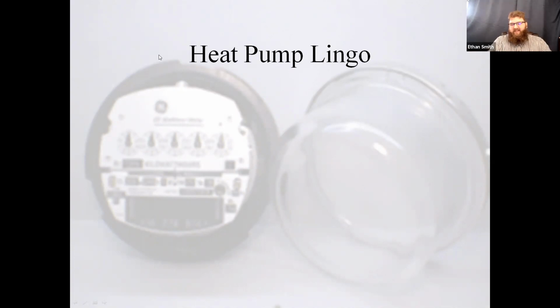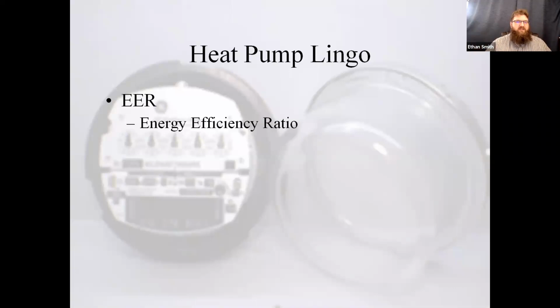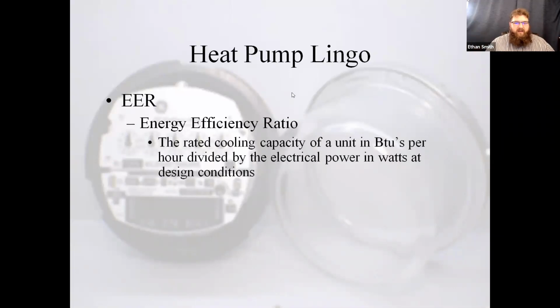Okay, so heat pump lingo, guys. There's a few terms that we need to be familiar with if we're gonna talk about heat pumps in an intelligent fashion. So let's get some of the vocabulary out of the way here. EER is a term we use more commonly in heat pump specific, and that's just the energy efficiency ratio. So this is a momentary glimpse of how efficient the unit is rather than the SEER rating, which would be a seasonal energy efficiency ratio over time. And it's simply BTUs per hour divided by the electrical power in watts. So it's BTUs per watt. Typically used to rate compressor efficiency, PTAC efficiencies. You'll have EERs on them, and then we use EER in some of our capacity calculations and other calculations that we use.